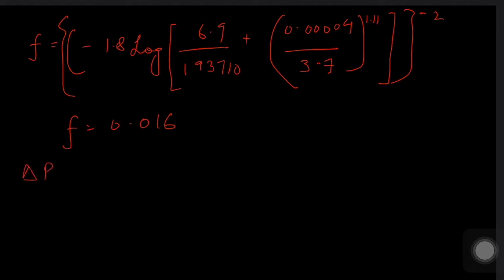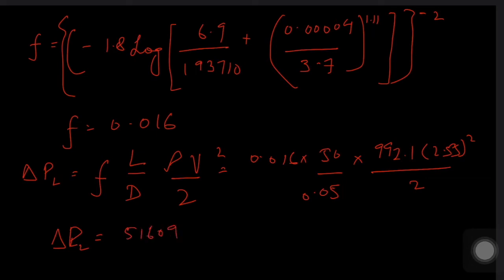Now that we know the friction factor, we use the pressure loss formula — valid for both turbulent and laminar flow: ΔP_L = f × (L/D) × (ρV²/2) = 0.016 × (50/0.05) × 992.1 × (2.55²/2), giving a pressure loss of approximately 51,609 Pa, or 51.6 kPa.